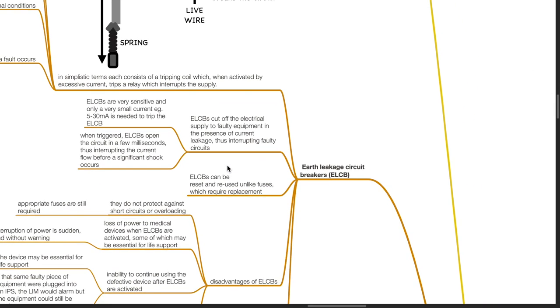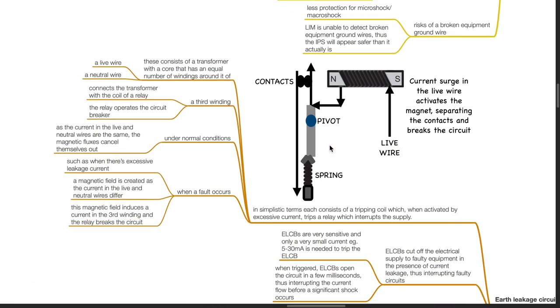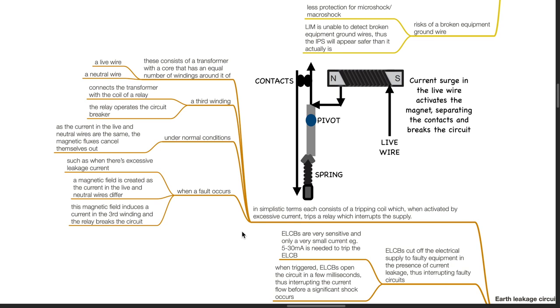Earth leakage circuit breakers. In simplistic terms, each consists of a tripping coil which, when activated by excessive current, trips a relay which interrupts the supply. This consists of a transformer with a core that has an equal number of windings around it of a live wire and a neutral wire. A third winding connects the transformer with the coil of a relay. The relay operates the circuit breaker. Under normal conditions, as the current in the live and neutral wires are the same, the magnetic flux of each cancel themselves out. When a fault occurs, such as when there is excessive leakage current, a magnetic field is created as the current in the live and neutral wires differ. This magnetic field induces a current in the third winding and the relay breaks the circuit.